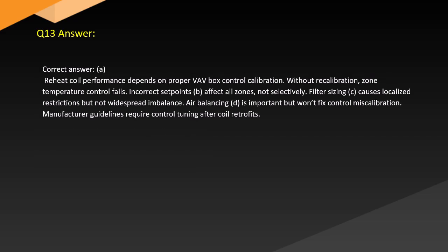Answer. Correct answer: A. Reheat coil performance depends on proper VAV box control calibration. Without recalibration, zone temperature control fails. Incorrect set points, B, affect all zones, not selectively. Filter sizing, C, causes localized restrictions but not widespread imbalance. Air balancing, D, is important but won't fix control miscalibration. Manufacturer guidelines require control tuning after coil retrofits.